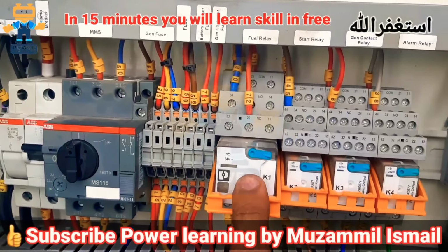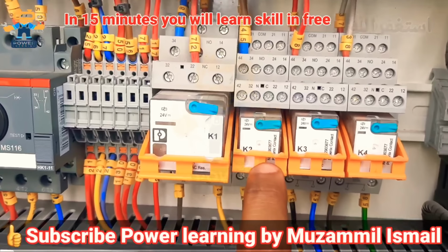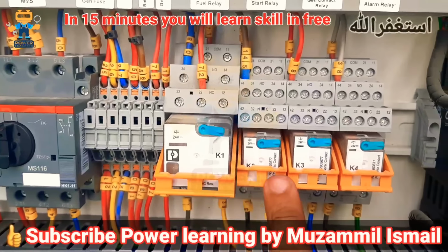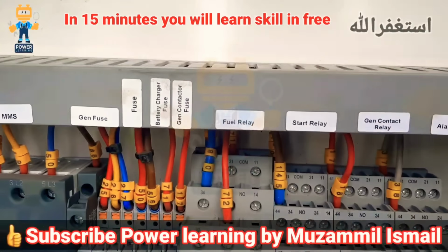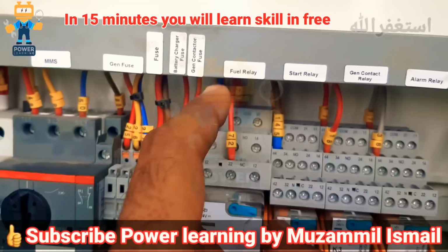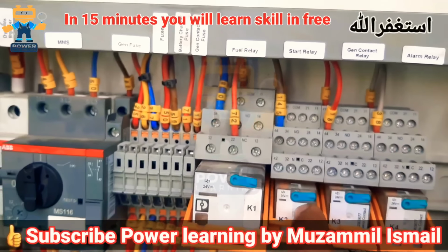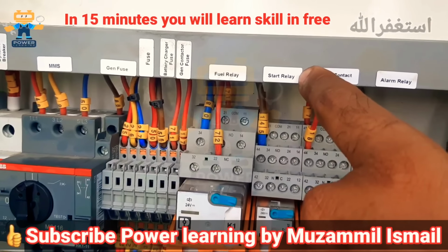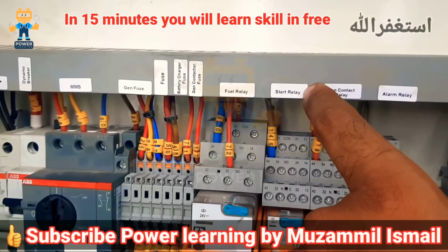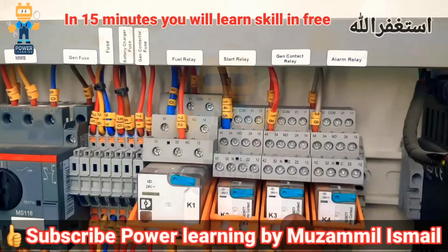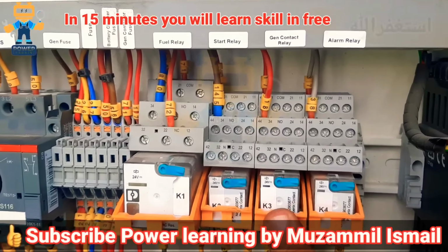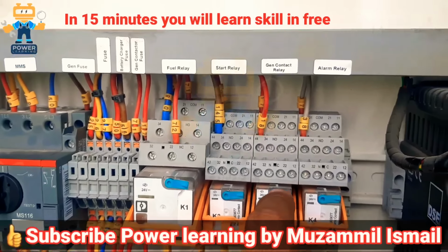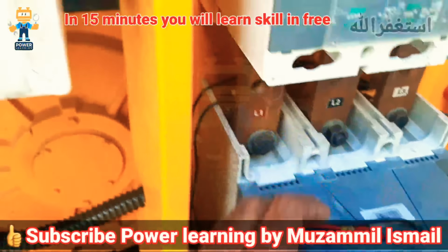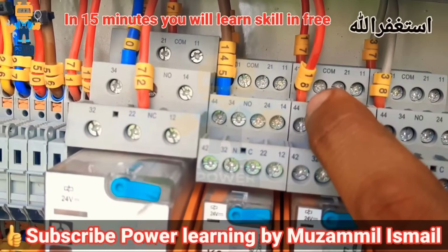After that here we have the K1 relay, and this is K2, K3, K4. What is the function of K1, K2, K3, K4? Here it is written fuel relay, so once this relay is energized, the generator fuel is on. This relay is for the starter motor, which runs only for 5 to 6 seconds and then opens. This is the generator contact relay. Once the generator is ready and the breaker is closed, this relay will close your main contactor. Here it is written 18, and this is the 18 number wire, closing our main contactor.